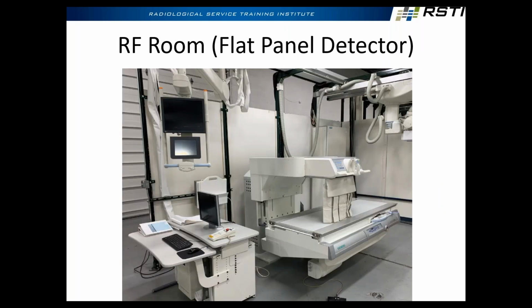And then, you know, to your point, here's a modern system. So we teach the Siemens, what is this, Luminos Agile. So this is an R&F room. What do you notice is missing? There's no II. So right here, you can't see it, but here's the over table tube, right? Here's the under table tube right there, you can see it. And there's no II. How come? It's a flat panel detector. So now manufacturers are getting away from that technology and replacing them with flat panels.